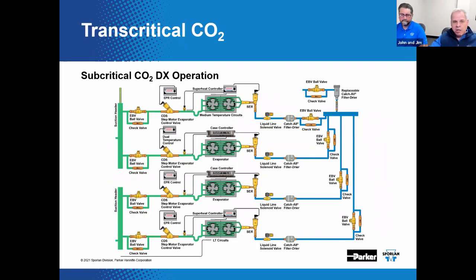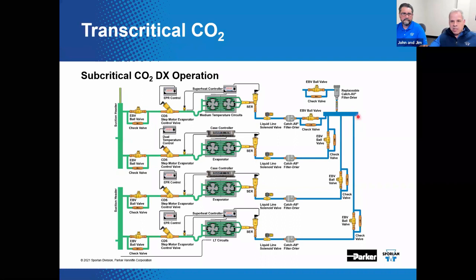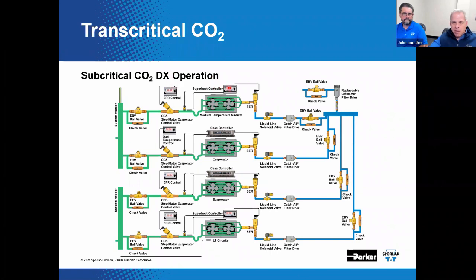This section should look familiar. This part of the system is very similar to the subcritical CO2 DX operation. Liquid from the liquid vapor separator, got to find it up here, I guess. Is that it up there? It supplies CO2 to the electrically actuated, electronically controlled expansion valves over here. These valves control superheat with either superheat controllers or case controllers. Here you see some controllers depicted. The evaporator pressure is controlled with electrically actuated, electronically controlled evaporator pressure regulators in the same manner. And you see those controllers and these valves over there.